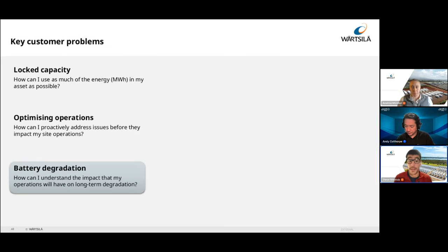Before diving deeper, I want to talk about drivers of degradation. The first is depth of discharge: the percentage of total capacity used during an operation. If your battery is at 80% and you discharge all the way down to 0, that's an 80% depth of discharge. If it's at 70% and you discharge down to 20%, that's a 50% depth of discharge. Generally, the higher the depth of discharge, the greater the rate of degradation. The highest possible, 100% down to 0%, has the most significant impact. Many frequency market applications, with the asset fluttering between 40 and 60%, have a lower impact on degradation.